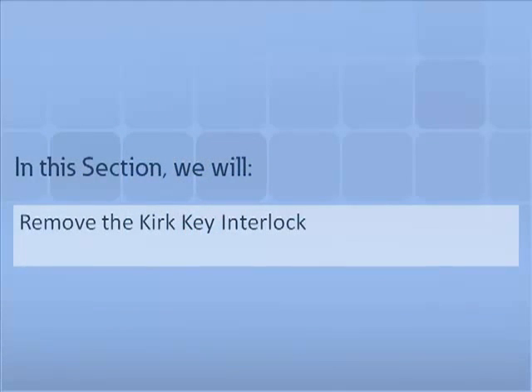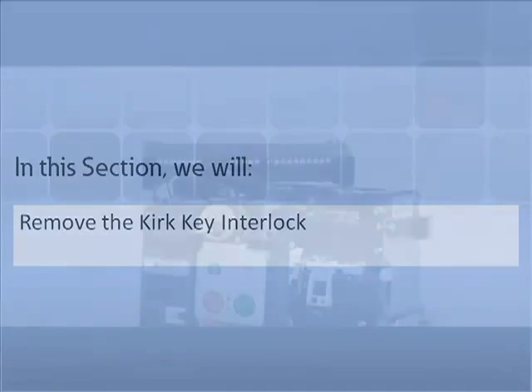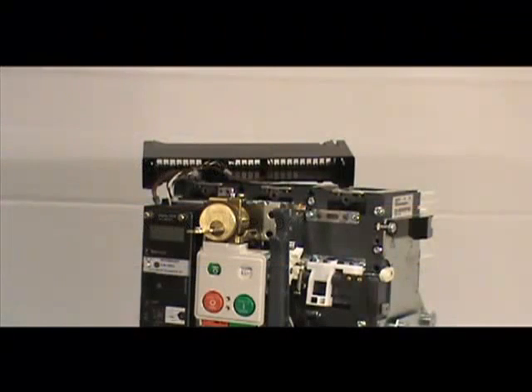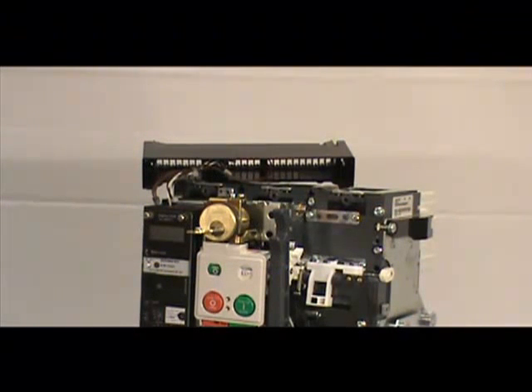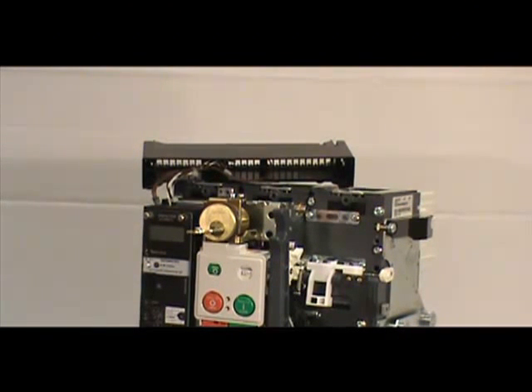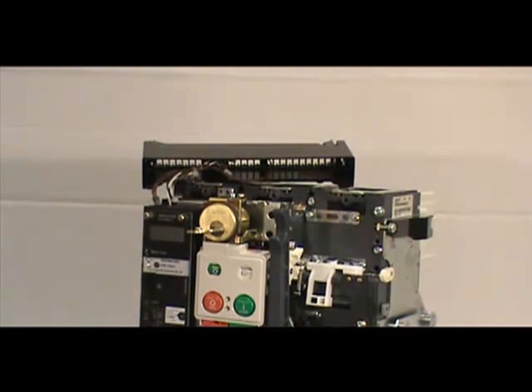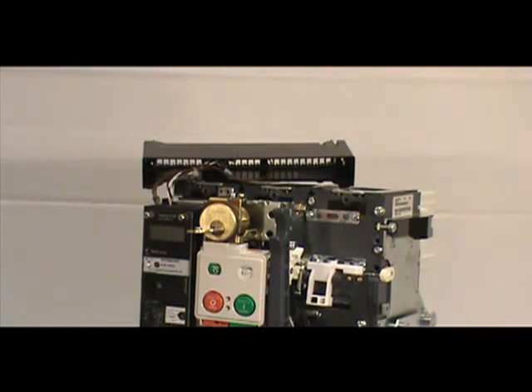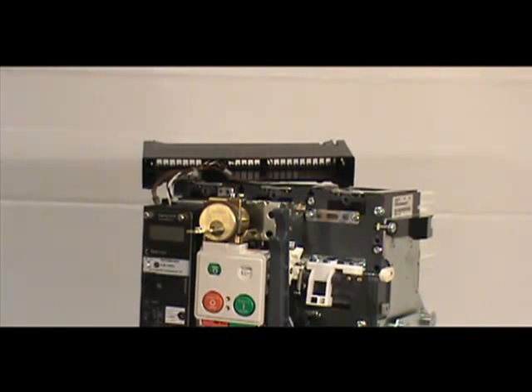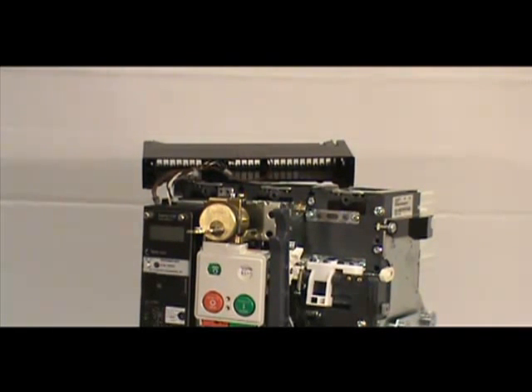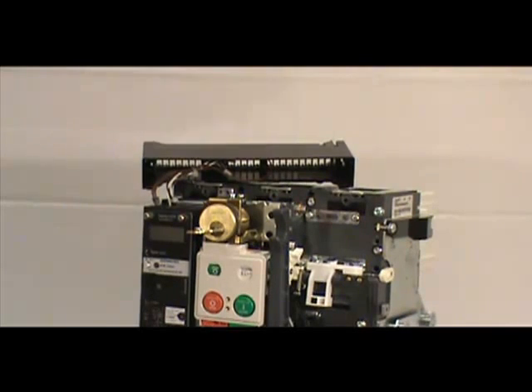In this section, we will demonstrate how to properly remove the Kirk key lock from the series NRX breaker. First, remove the cover and loosen the secondary mounting bracket. We demonstrated these processes earlier in the video. Next, use the number two Phillips head screwdriver to loosen the two mounting screws, then remove the mounting bracket and key lock from the mounting location.